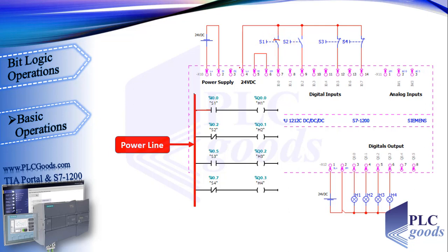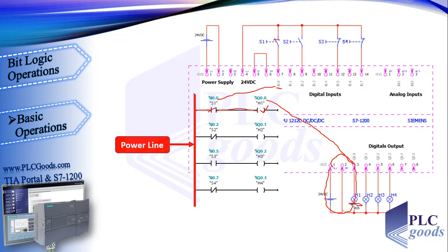If we press the push button, the 24V DC reaches I0.0. Then the state of this contact with I0.0 address changes to 1 or true, so its normally open state changes to close. Now the virtual power can reach to this coil with Q0.0 address, which refers to the first PLC output. So the PLC changes its state and lets the 24V DC turn on the H1 lamp. Briefly, reaching 24V DC to our digital inputs is the same as pressing push buttons in real.